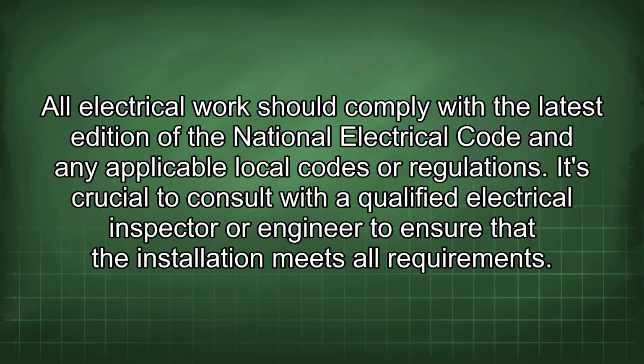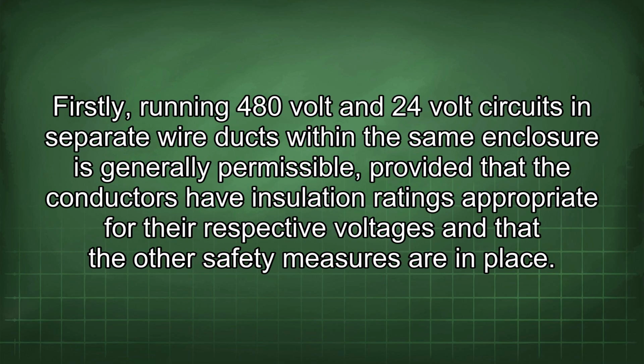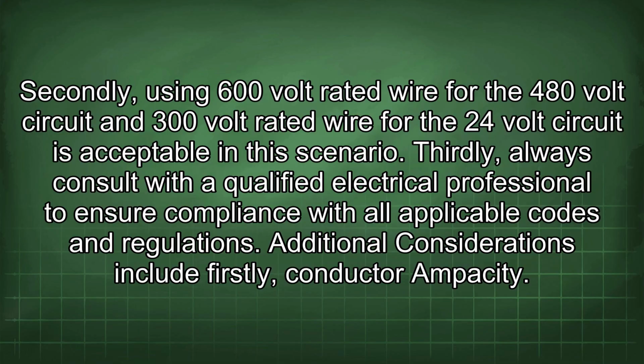meets all requirements. Firstly, running 480-volt and 24-volt circuits in separate wire ducts within the same enclosure is generally permissible, provided that the conductors have insulation ratings appropriate for their respective voltages and that the other safety measures are in place. Secondly, using 600-volt rated wire for the 480-volt circuit and 300-volt rated wire for the 24-volt circuit is acceptable in this scenario. Thirdly, always consult with a qualified electrical professional to ensure compliance with all applicable codes and regulations.